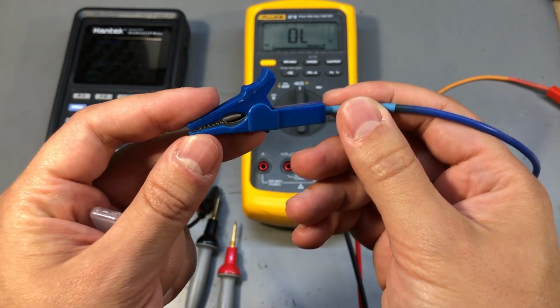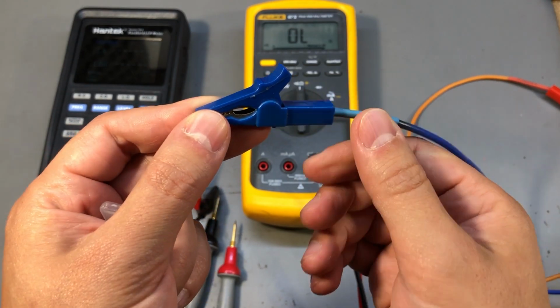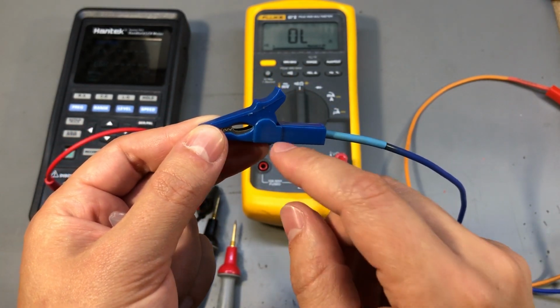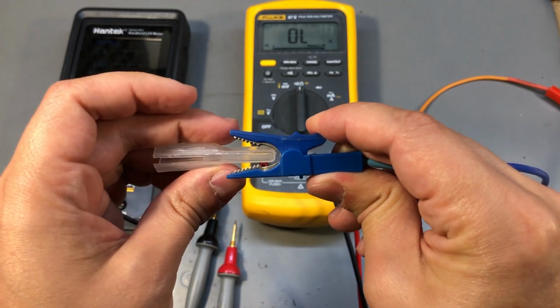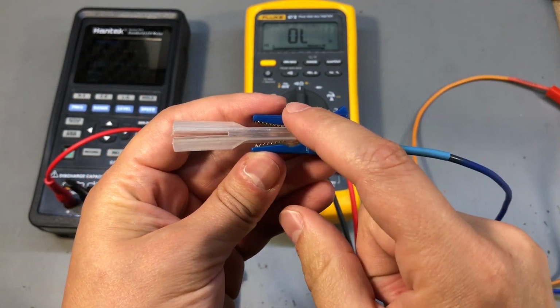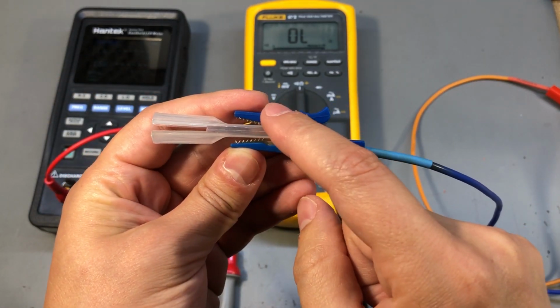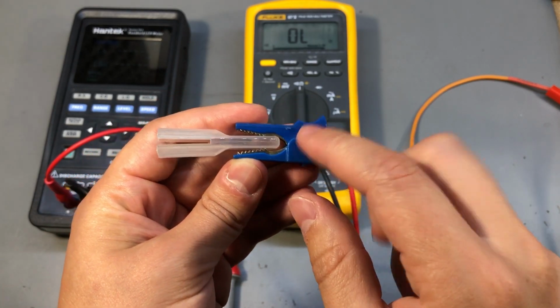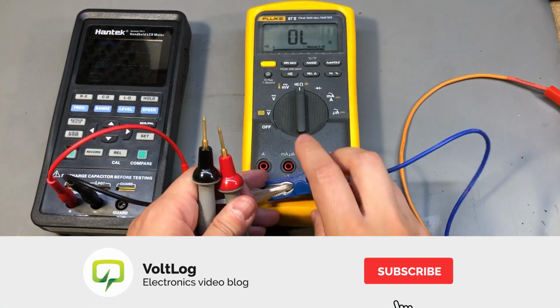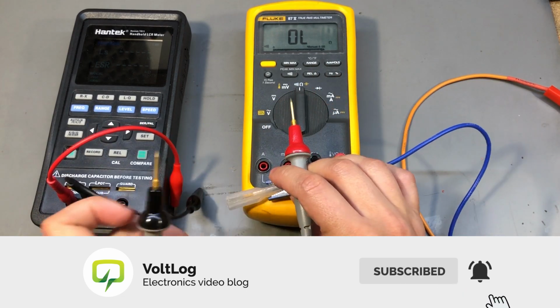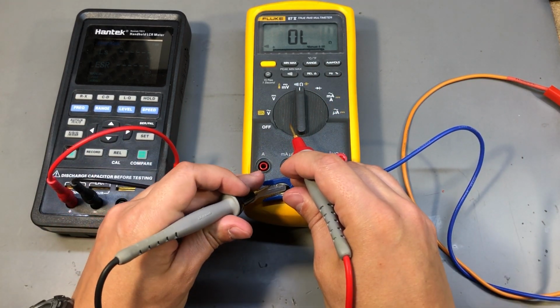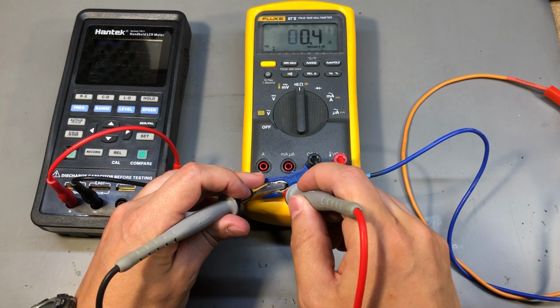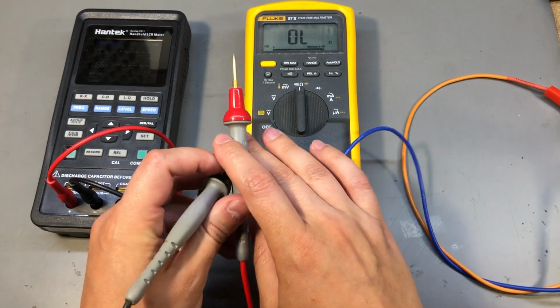A common mistake when building Kelvin 4-wire test leads is to use these standard alligator clips, because in a standard alligator clip, the top and bottom jaw are connected electrically at the hinge point. And let me prove that to you with the multimeter on the continuity tester. If I measure between the top jaw and the bottom, we have a continuity.